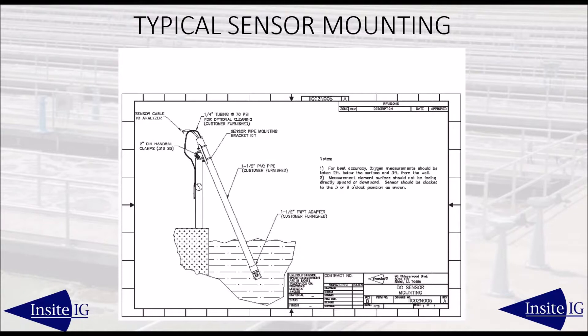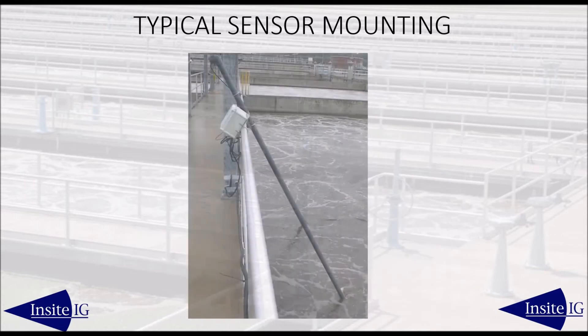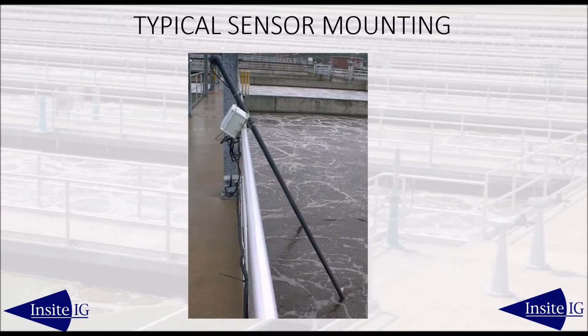The most common sensor mounting is right on the handrail, usually mounted one to two feet deep and at an angle to keep the sensor away from the submerged walls or structures. Insite offers a stainless steel mounting bracket that allows the sensor to be removed from the process without the use of any tools.